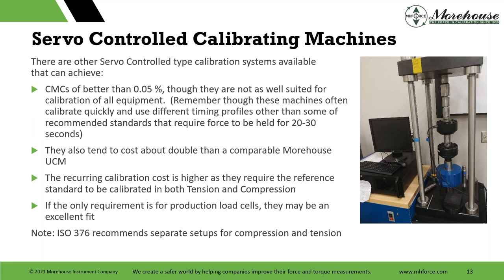So other types of machines, servo-controlled calibrating machines. CMCs are better than 0.05. They're not well suited for calibration of all equipment. Often they calibrate quickly and use different timing profiles other than some that are recommended by standards. Some standards require the force to be held for 20 to 30 seconds. These machines can do it, but people do not set them up to do that. And the ability to hold force is questionable for some of them.